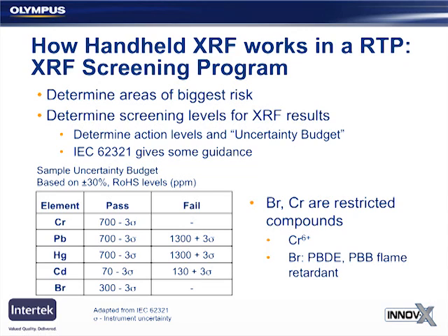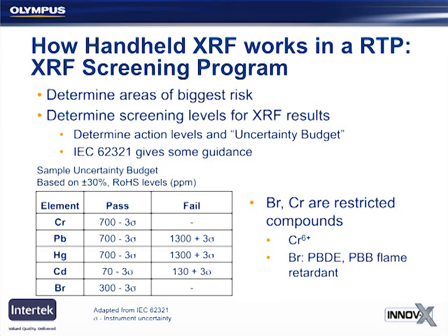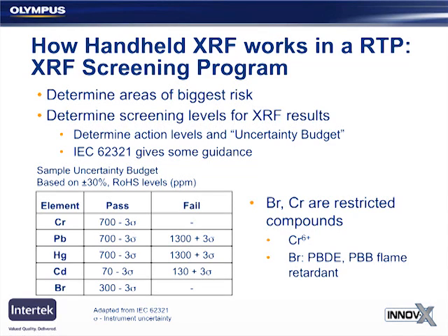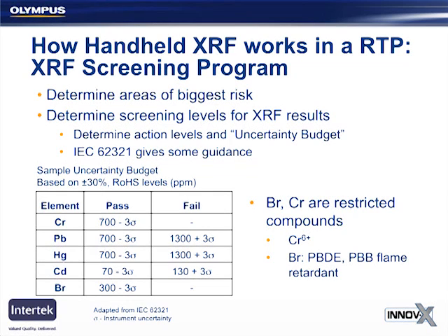Notice also that bromine and chromium are treated differently in this testing scheme. Bromine and chromium, again, this testing scheme is for RoHS specifically. Those two elements are not restricted elements. They're restricted in certain chemical forms. So chromium is restricted as hexavalent chromium, and bromine is restricted in certain flame retardants. XRF can tell you the total elemental content for these elements, but it can't tell you what chemical form they're in or what molecules they're bound in. So you can use an XRF result for those elements to say that a sample passes if you have a very low result for those elements, but if you detect higher levels of those elements, you may need to do some additional testing.